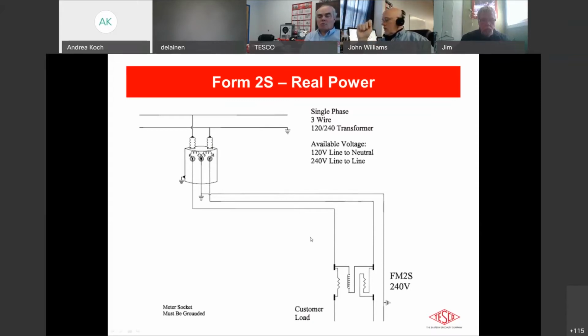One thing to keep in mind here as I talk about the test application for each of these meter forms, and how that applies to what Tom spoke about earlier in terms of Blondel and things like that. The test board is built to create, when you're testing pure accuracy per ANSI C12, the potential and the current in a very highly regulated way so that all the loads are always balanced perfectly when you select to do so. All the ANSI specifications say how far that can deviate per channel, but basically we're creating the absolute perfect conditions so as to zero out any Blondel type error.